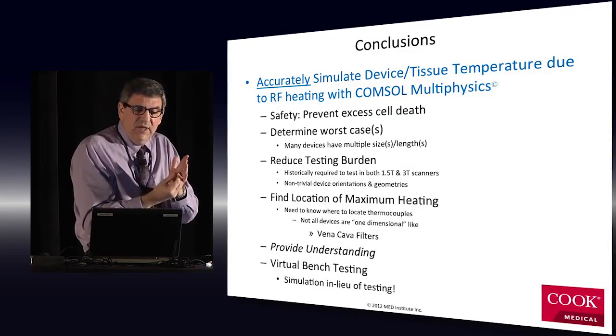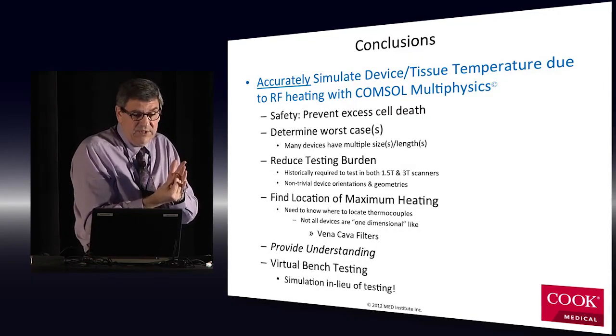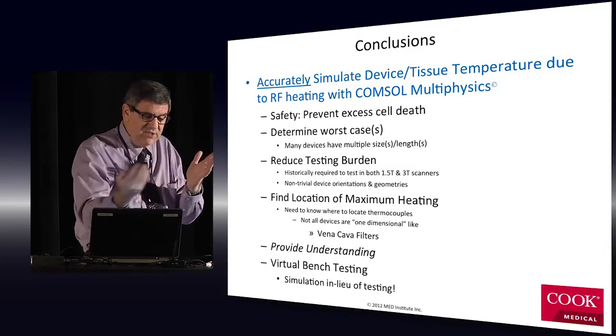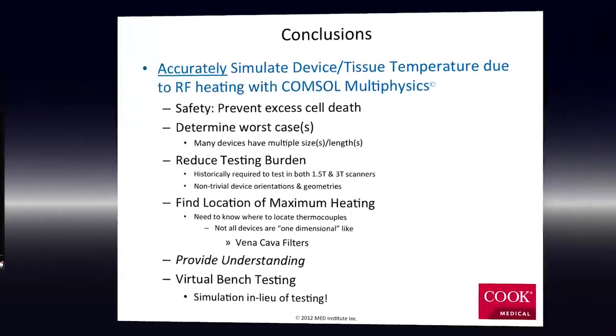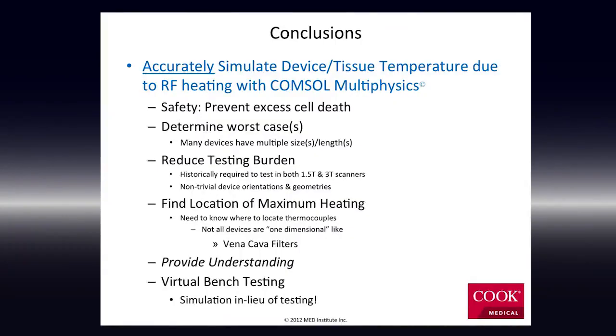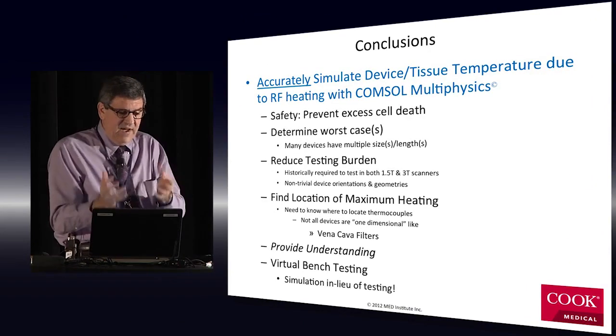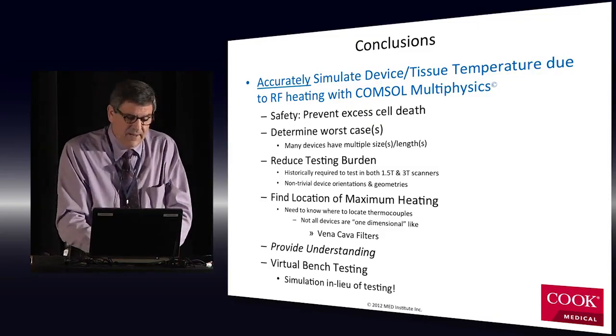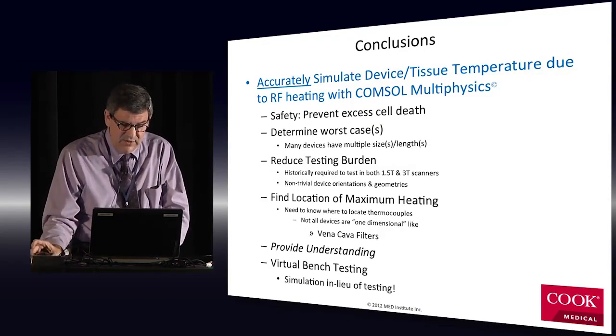simulate that temperature, validate it with various experiments now, and then be able to, it's the same slide I had before, we can determine safety. We can use it to supplement or complement the testing. We can find the locations of maximum heating. It gives us an understanding of how a certain device may perform in the phantom, and eventually, where I'm going with this, potentially in vivo. So it can provide us all the things we were looking for. And I've changed the question mark here to an exclamation mark.